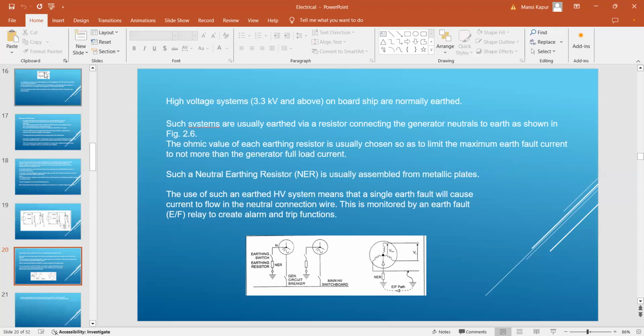Such systems are usually earthed by a resistor connecting the generator neutral to earth, as shown in the figure. The ohmic value of the earthing resistor is usually chosen so as to limit the maximum earth fault current to not more than the generator full load current. So you have to put this resistor in such a manner that it will not increase the generator full load current.